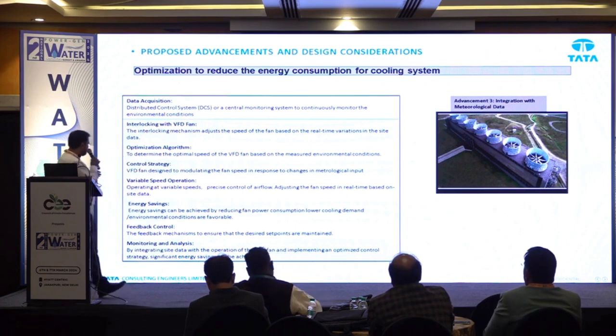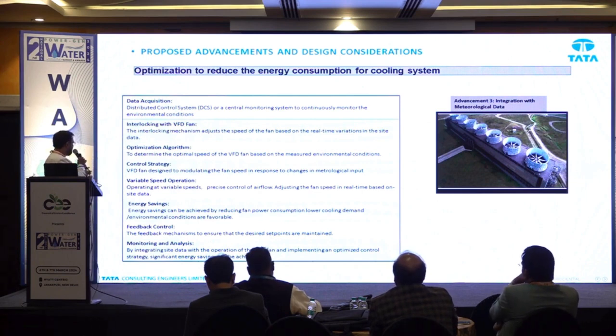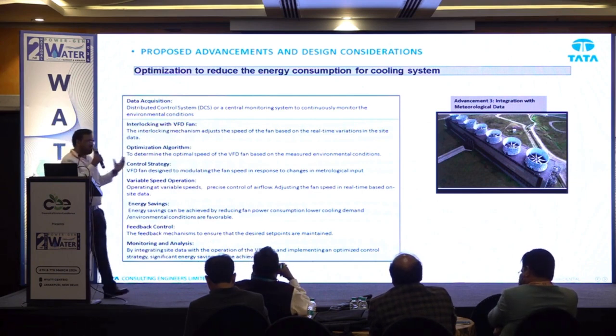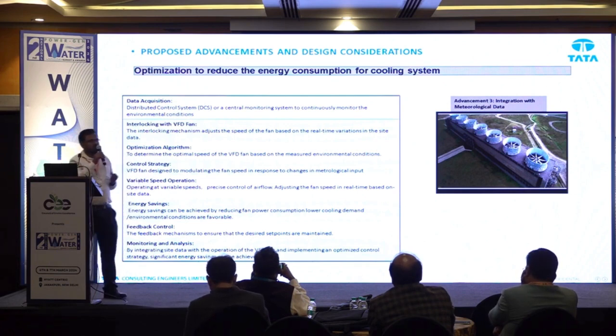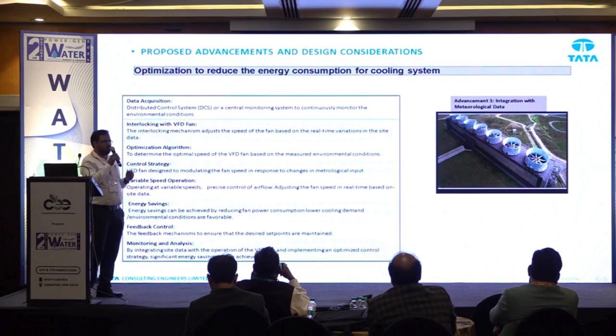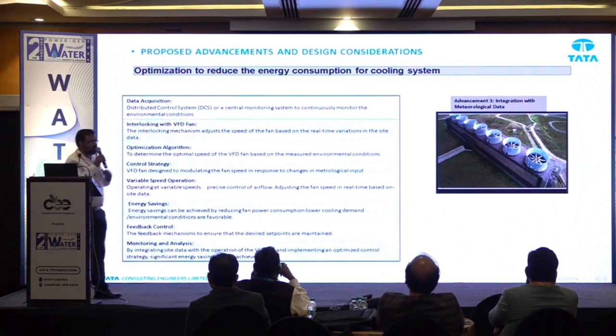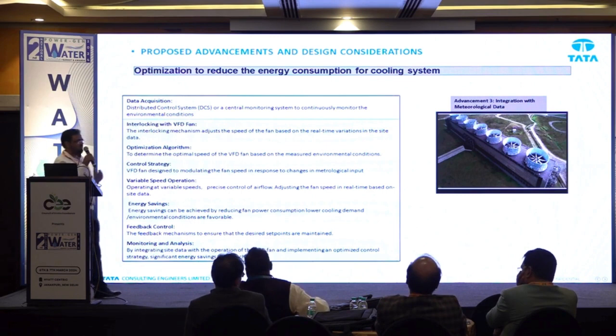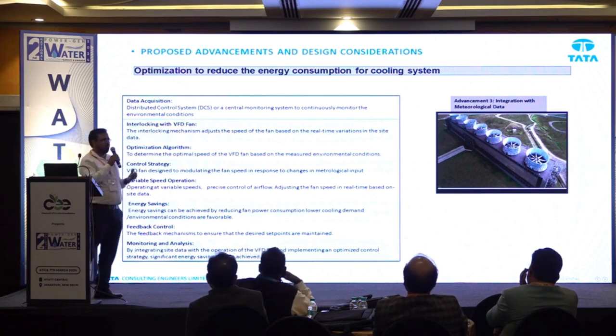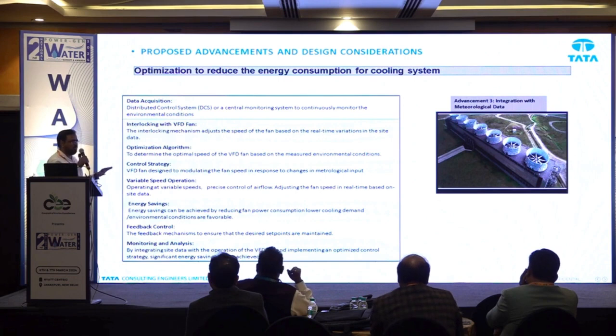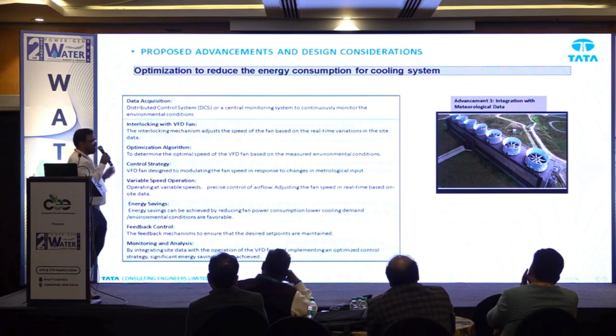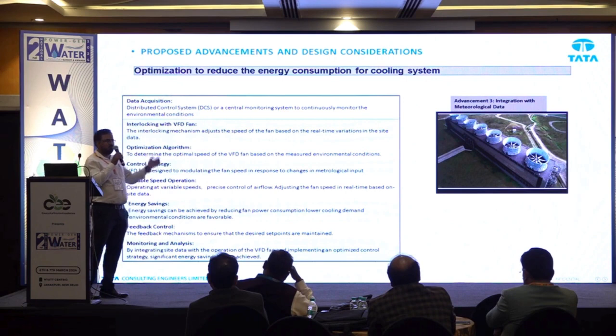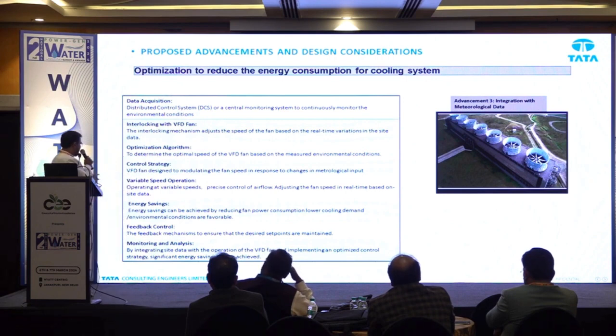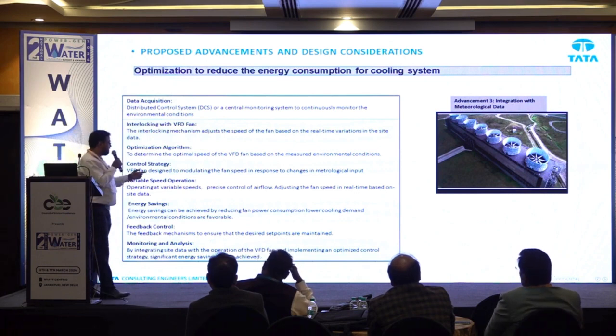Variable speed operation means precise control of air flow, adjusting the fan speed in real time based on the site data. This variable speed will be achieved based on the simulations. Based on the simulation model, whatever input comes for the air distribution field has to be integrated along with the OEM. Then this data can be interlocked with the DCS to get the input from meteorological data and operate the fan based on demand. So that is the variable speed operation.